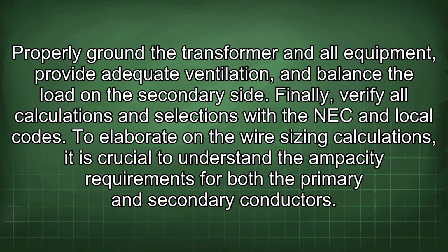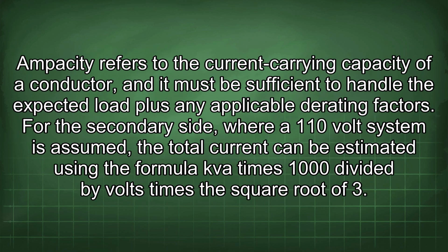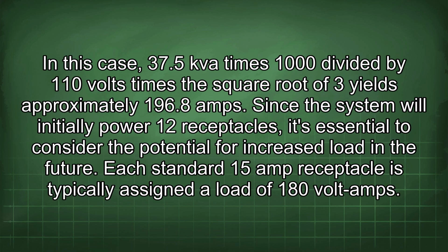To elaborate on the wire sizing calculations, it is crucial to understand the ampacity requirements for both the primary and secondary conductors. Ampacity refers to the current carrying capacity of a conductor, and it must be sufficient to handle the expected load plus any applicable derating factors. For the secondary side, where a 110-volt system is assumed, the total current can be estimated using the formula kVA times 1000 divided by volts times the square root of 3. In this case, 37.5 kVA times 1000 divided by 110 volts times the square root of 3 yields approximately 196.8 amps. Since the system will initially power 12 receptacles, it's essential to consider the potential for increased load in the future. Each standard 15-amp receptacle is typically assigned a load of 180 volt amps.